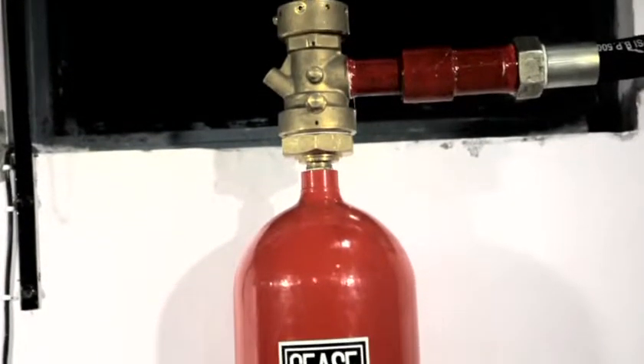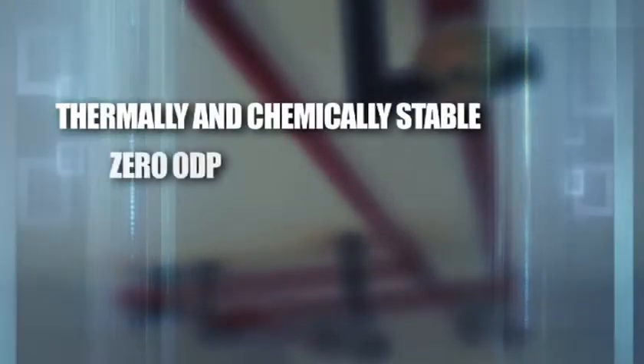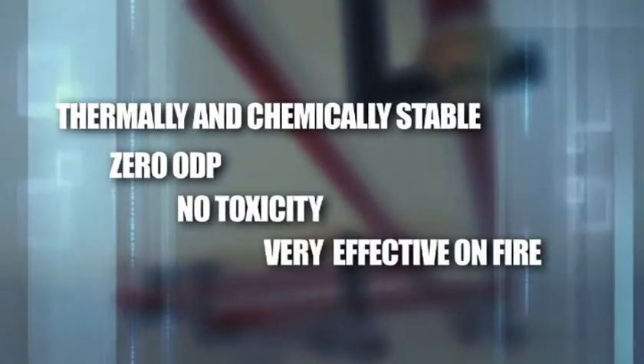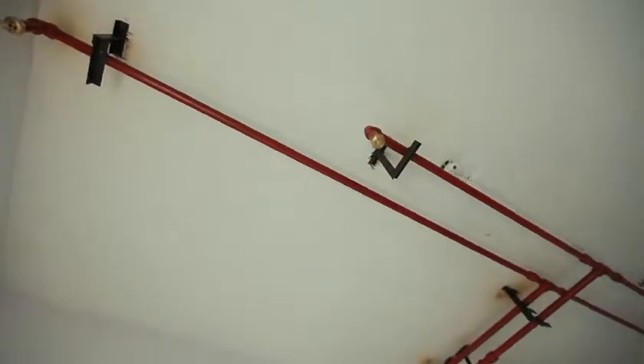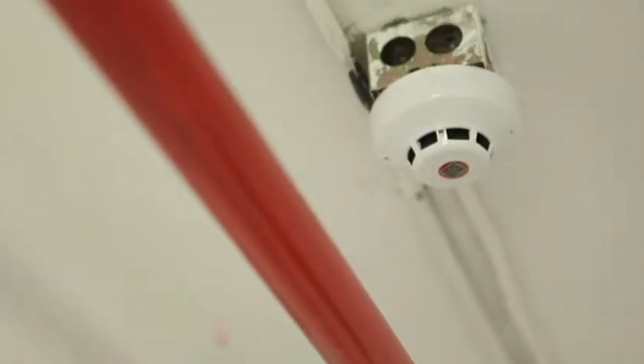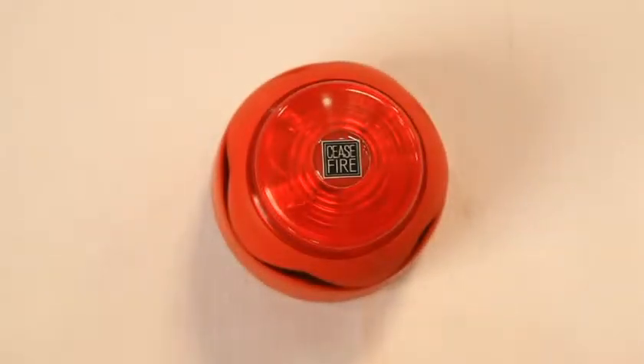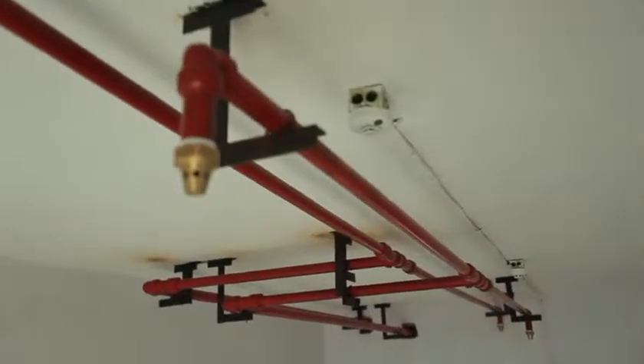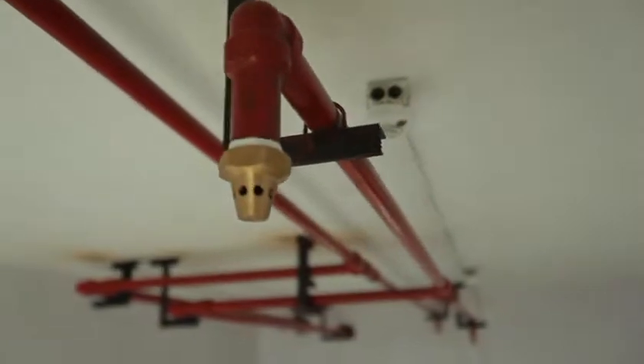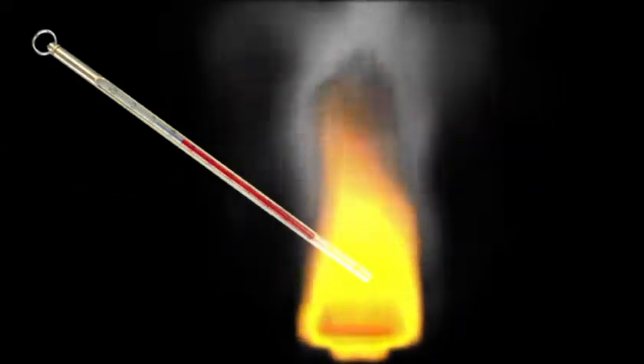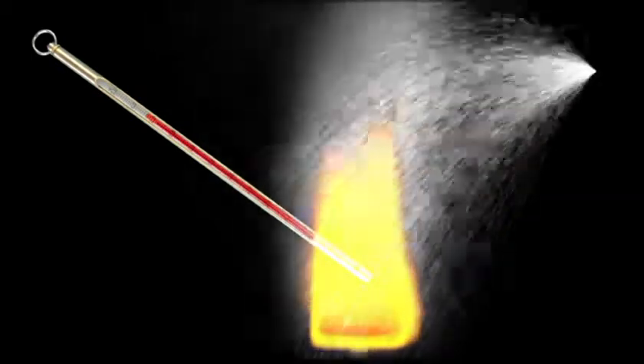FM-200 is a colorless and odorless gas that has been liquefied under pressure. It is thermally and chemically stable, zero ODP, no toxicity, and very effective on fires. This powerful automated flooding system is designed and equipped to initiate firefighting within seconds of the fire being detected, without causing any collateral damage. FM-200 attacks a fire with a two-pronged approach: it absorbs the heat from the fire, bringing down temperatures and preventing reignition, and the fluorine radical in FM-200 reacts with the flame, putting it out completely.